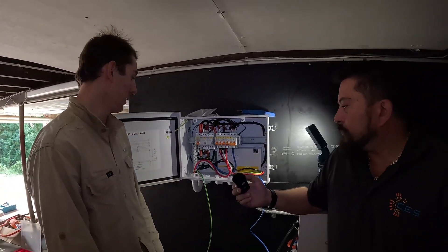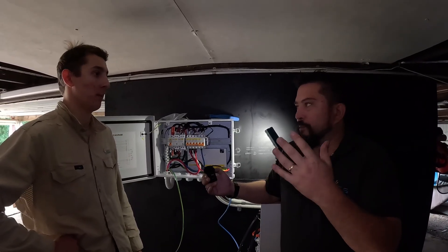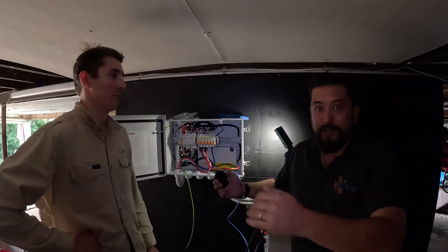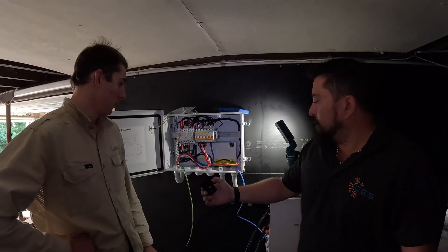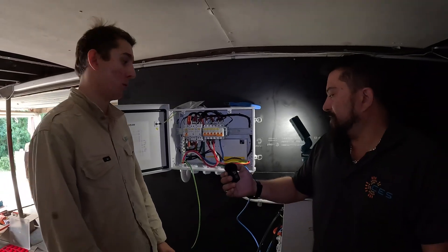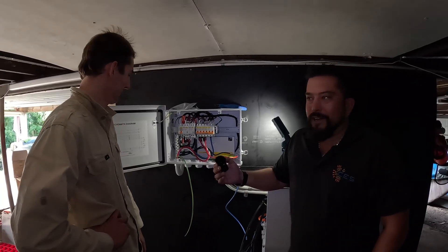The reason for going to 16mm cable is mostly due to voltage drop, because we've got a fair run to the main switchboard. That's a factor anyone should consider - the further you are from the switchboard, the cable material costs skyrocket, and copper's not cheap these days. That plays a part in your design to make sure the desired battery location is affordable while meeting all codes and requirements. We've also got a data comms cable here that talks to the inverter, which will be plugged in before commissioning, giving us the smarts to control the contactor and everything in the gateway.